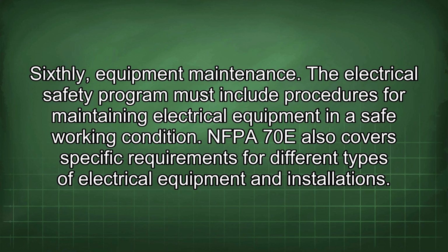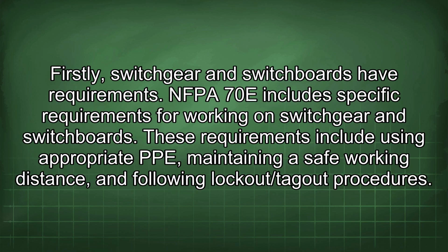NFPA 70E also covers specific requirements for different types of electrical equipment and installations. Firstly, switchgear and switchboards have requirements. NFPA 70E includes specific requirements for working on switchgear and switchboards. These requirements include using appropriate PPE, maintaining a safe working distance, and following lockout/tagout procedures.